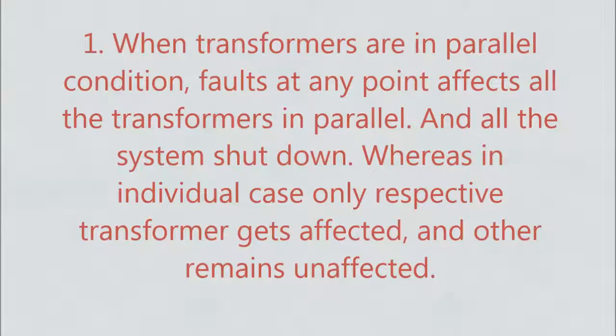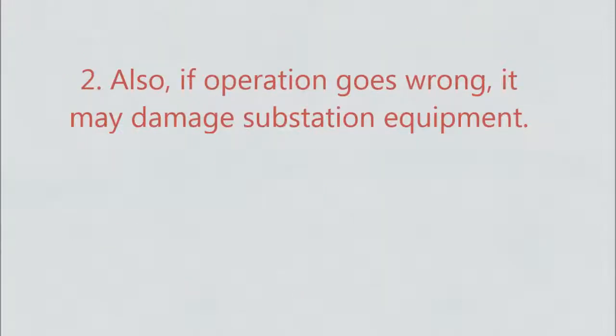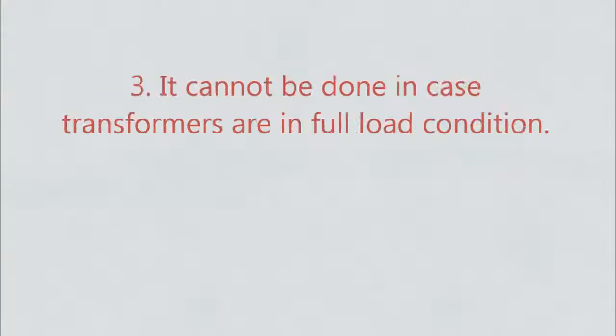Cons: First, when transformers are in parallel condition, a fault at any point affects all the transformers in parallel and the entire system shuts down — whereas individually, only the respective transformer would be affected and the other would remain unaffected. Second, if the operation goes wrong, it may damage substation equipment. Third, parallel operation cannot be done if the transformers are already in full load condition.